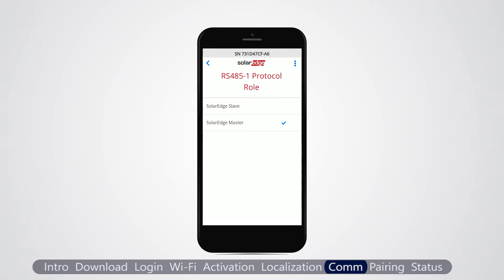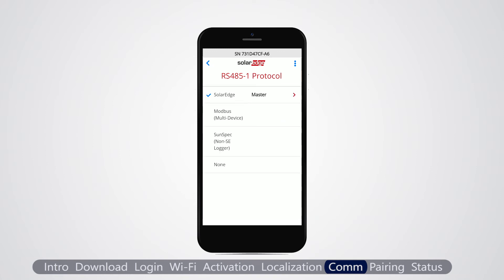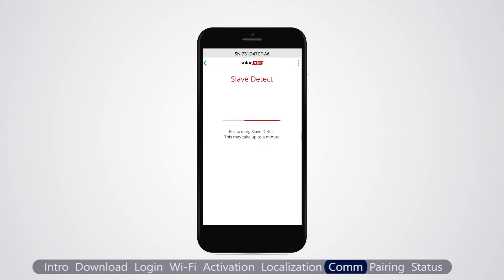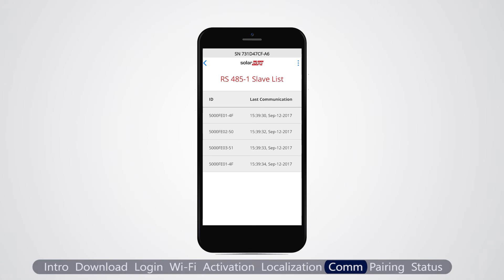Then select RS-485 bus, then select protocol: SolarEdge master. Select slave detect. The master inverter detects the other inverters on the bus and displays all detected serial numbers. Inverters that share an RS-485 bus can be configured simultaneously from the master inverter.